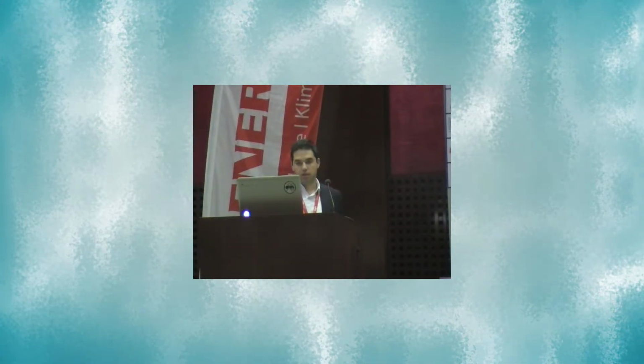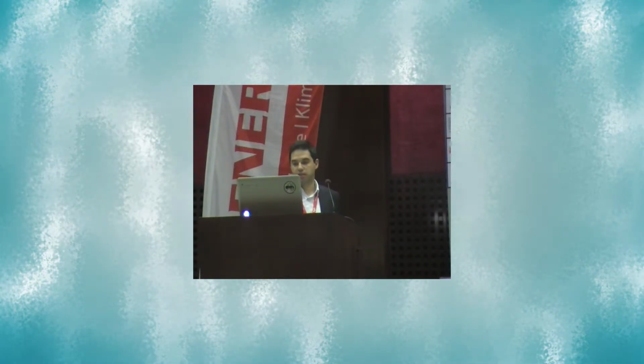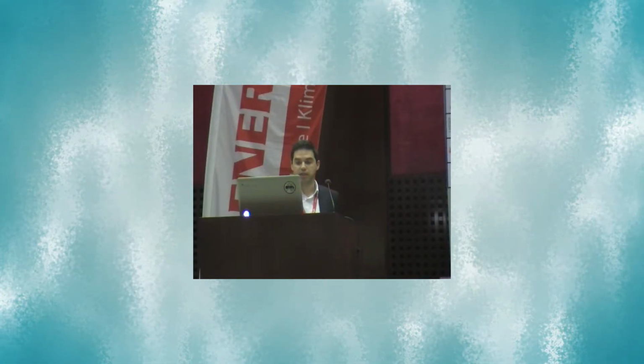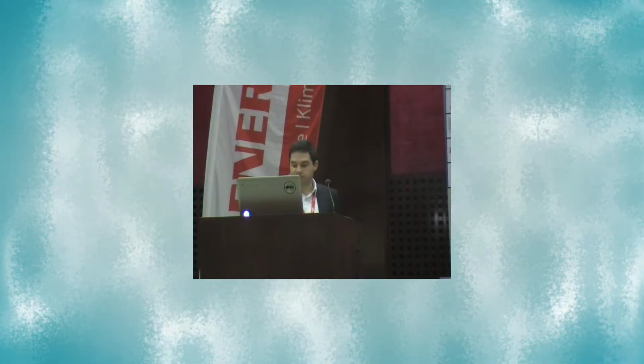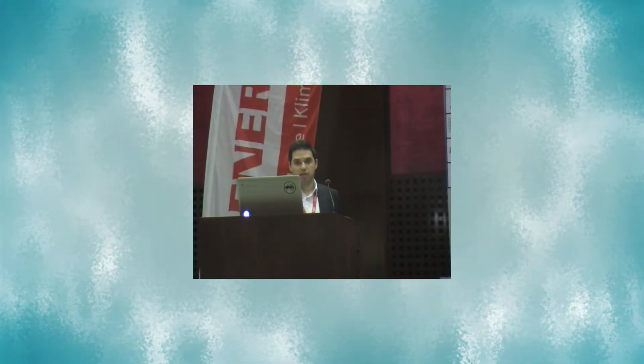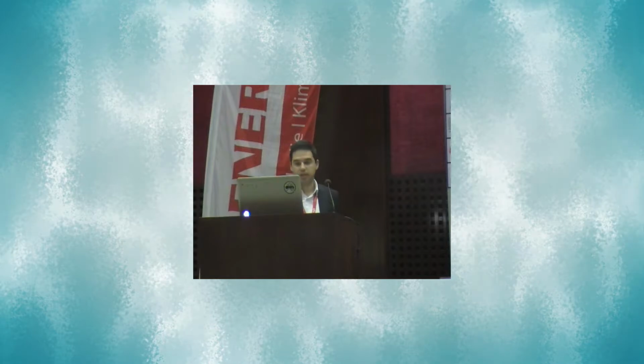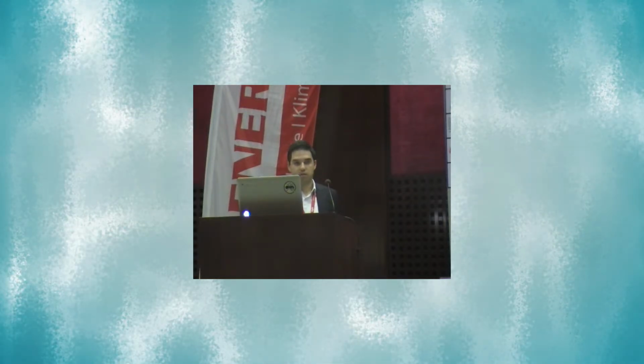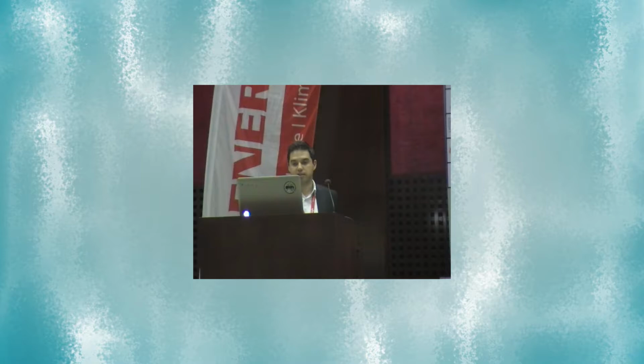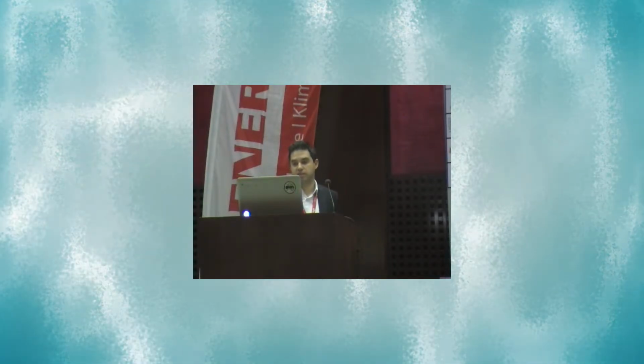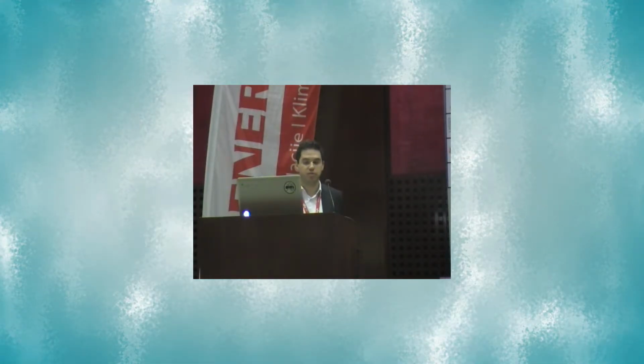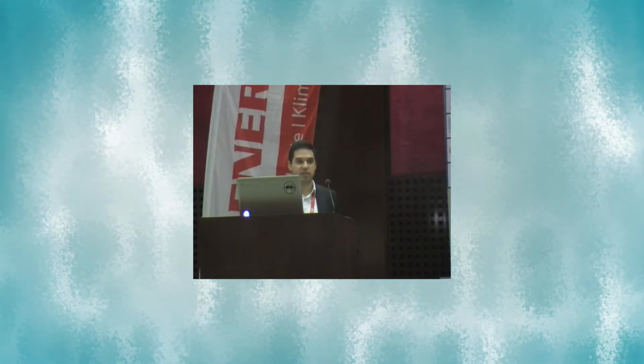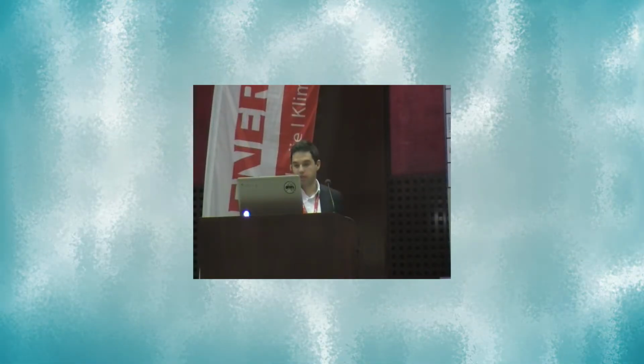So, as many presenters before spoke, CO2 or R744 is the most attractive, I can say, and most widely accepted solution for the new supermarket. The biggest advantage is that it's a natural refrigerant. The price is cheap, it's available. It has smaller pipes. The compressor has less swept volume, which means smaller compressors. We have a lot of excess heat energy which we can use.